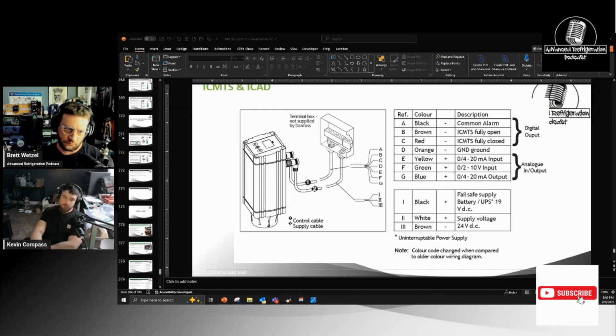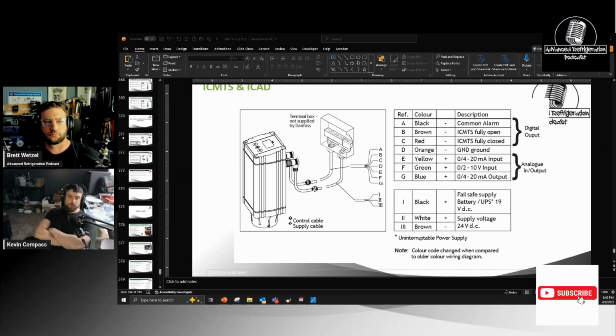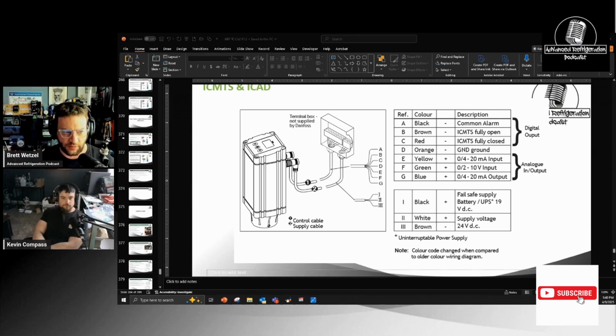In the wintertime, though, you may be open 60, 70%, especially if you're floating your head pressure down and you're not afraid to bring the head pressure down and let everything float down. You may be open more because your head pressure is lower. The closer you get to flash tank pressure, the more the valve's going to be open. Yeah, that makes sense. You're basically acting like a conventional commercial refrigeration system at that point, right? Because I've seen someone float it down as low as almost what the flash tank is. Correct.